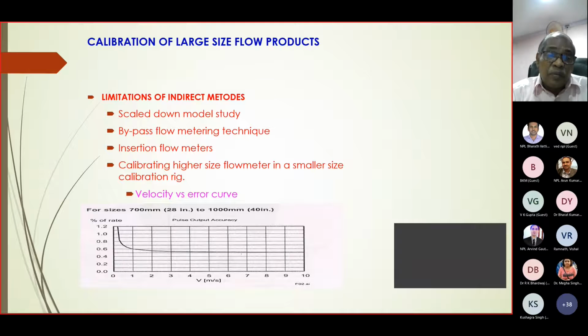Then I have to calibrate it, and I have to finalize a non-dimensional parameter. The non-dimensional coefficient I have to apply to the higher size also. There are uncertainties in that. Or you can go for a bypass technique, which is also not so accurate. Then insertion flow meters are another possible way.